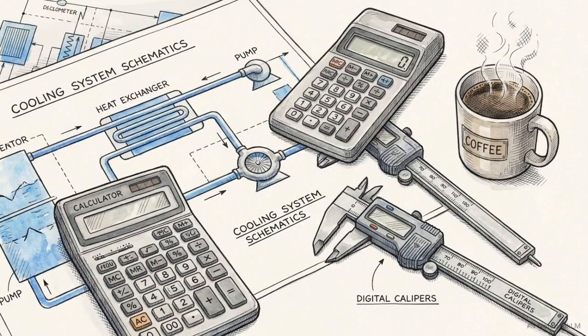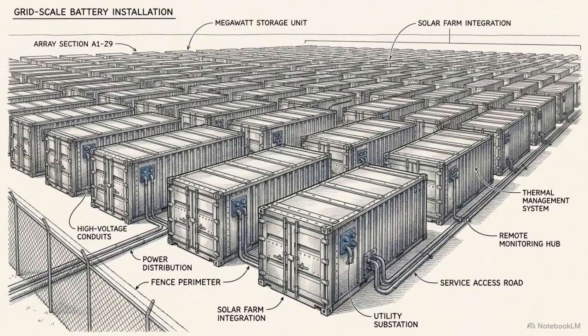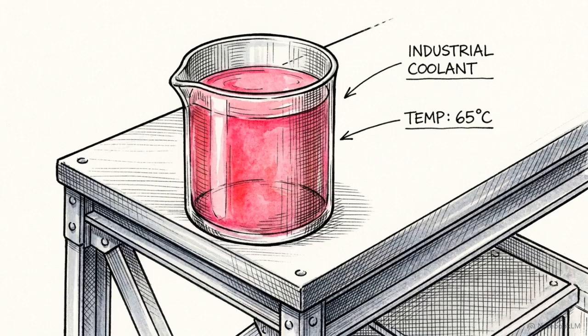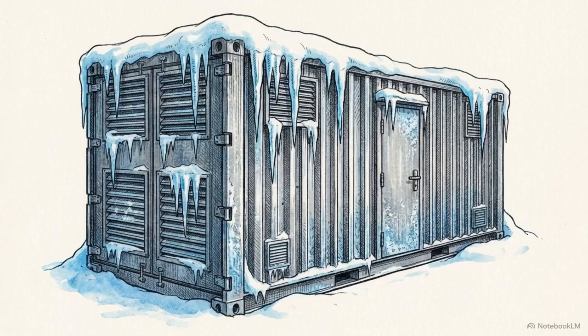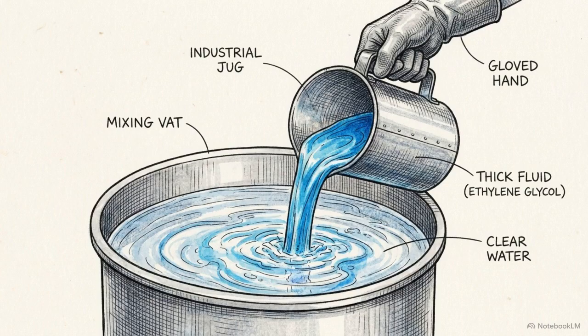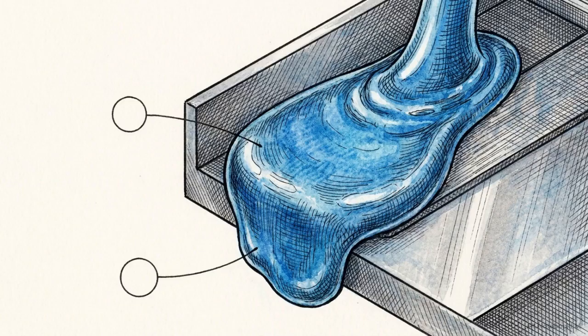Designing the primary loop is a delicate optimization problem. Engineers must balance the total cooling capacity of the fluid against the strict requirement for thermal uniformity across thousands of individual cells. Executing that specific mass flow rate requires selecting the correct working fluid. Pure water has excellent thermal conductivity, but an outdoor grid battery must survive winter climates. Engineers use a precise mixture of water and ethylene glycol, sacrificing a fraction of thermal transfer efficiency to guarantee critical freeze protection. But adding ethylene glycol increases the fluid's viscosity.